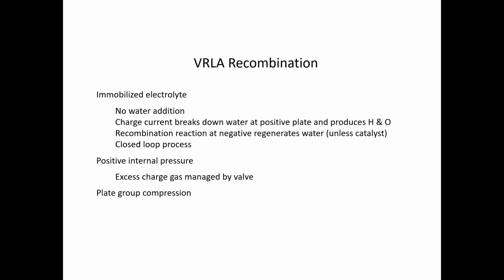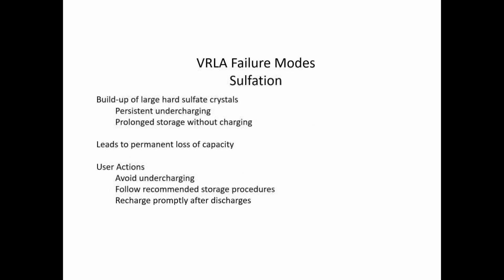I'll use Midtronics just because I believe that's a tester that you utilize. But that's what it's looking for. It's really looking for the conductivity between the most positive and negative terminals within that battery. So you're looking to see, hey, that battery is drying out, you're losing compression, you're getting sulfation on the plate. Any of those things that are going to impede the ability of that battery to perform what it's designed to do, that's picking up the resistance. Conductance is just the inverse of resistance, but that's what that test set is looking at, a bunch of different variables that can limit it.